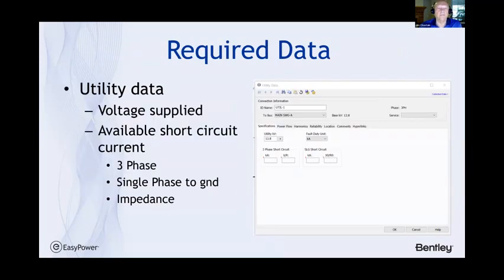The data that's required is loaded in the software. This is a screenshot of what's called the utility data dialog box. And probably as much as anything, this is an important element that you need to retrieve from the utility company, because the available short circuit current is the starting place for the fault if it occurs in your plant. So the available short circuit current, three-phase and single-phase impedance to ground, and the impedance of the three-phase fault are required.